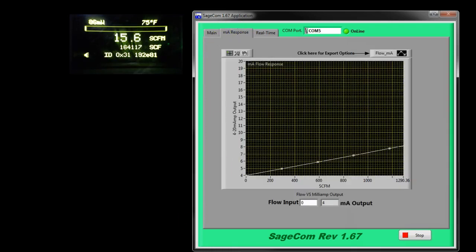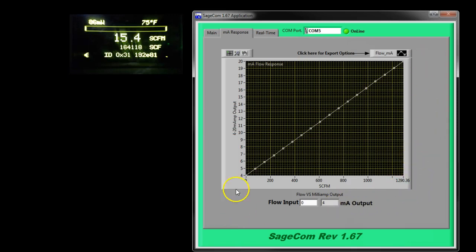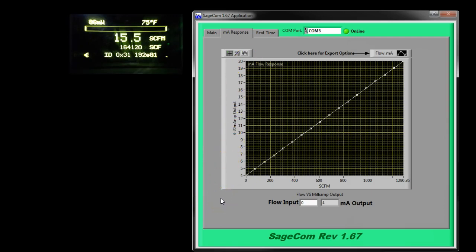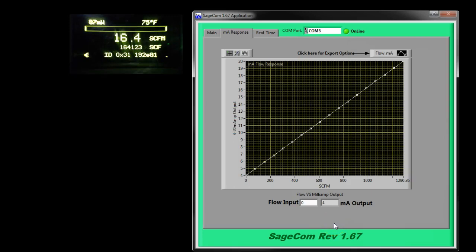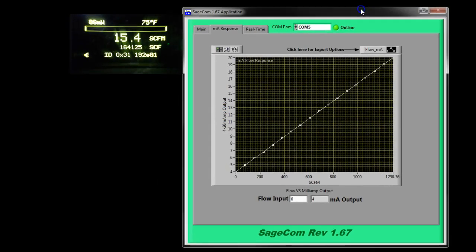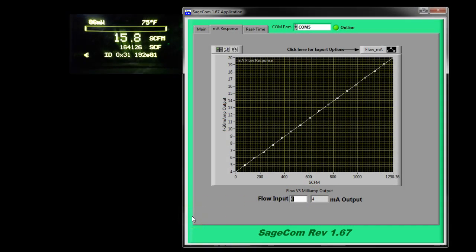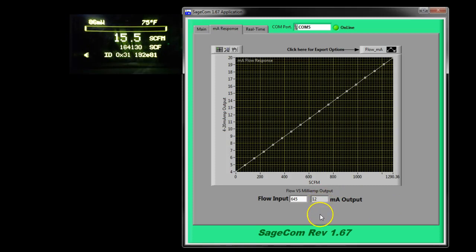Now, we're going to go to the milliamp response. And this particular chart is helpful for two reasons. You can see what the engineering units are versus the 4 to 20. But also, suppose you want to change the 20 milliamps going to the customer's computer or the customer's SCADA system. Well, you can actually do that. So, what I want to do here is I'm going to put a flow input that corresponds to half scale, roughly. Again, I'm going to press the return key. Notice I got 12 milliamps because I put in half the flow rate. And now I'm driving 12 milliamps throughout the plant. And they can check if they're hooked up correctly and so forth.